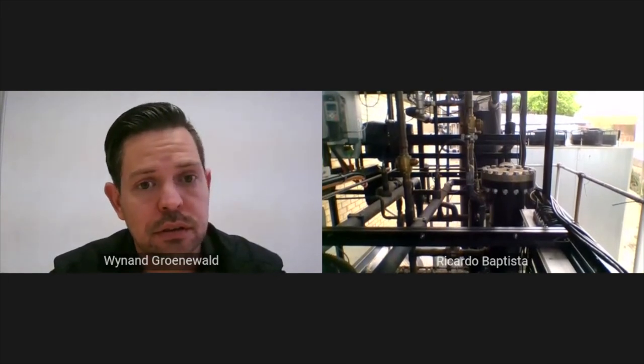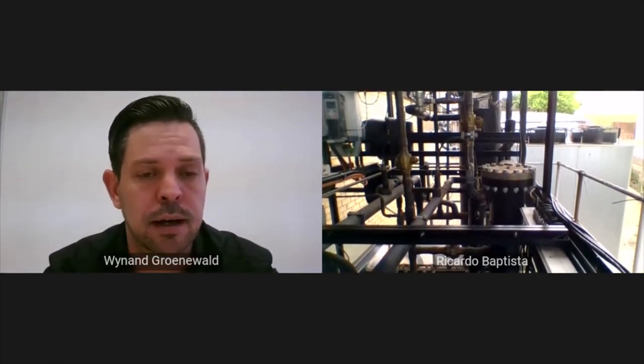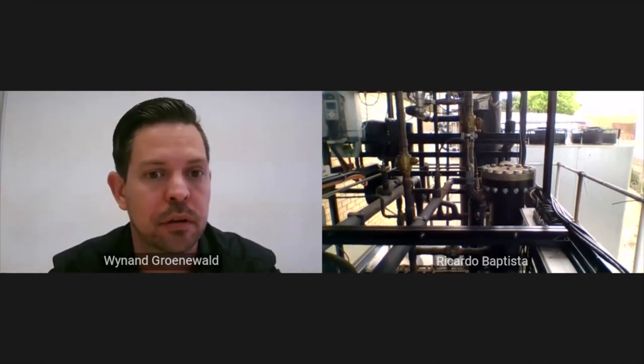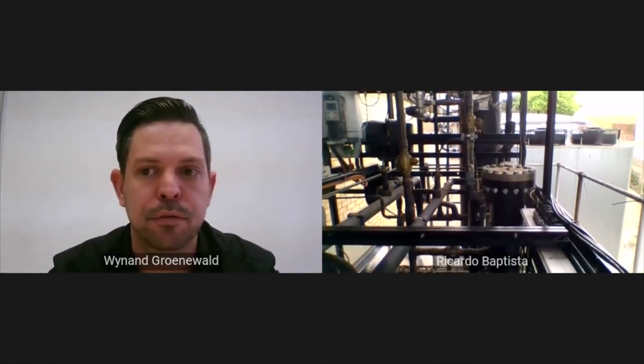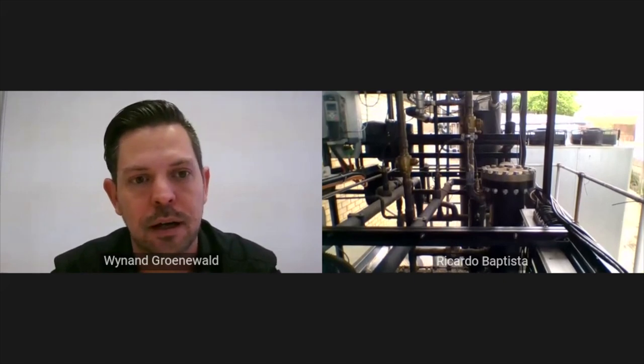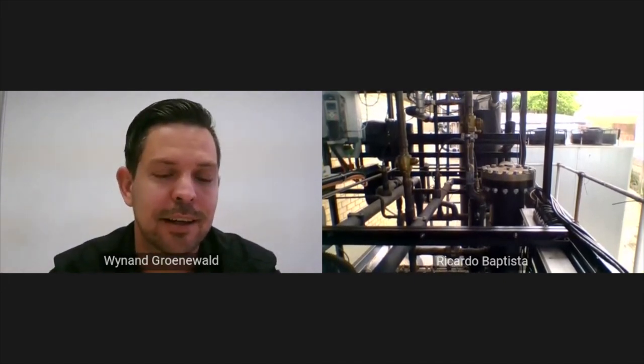When purging a CO2 system with CO2, while I'm on that topic, when starting up a system, it's always good to remember that CO2 has a very high triple point of about 5.18 bar. So good practice is to have vapor introduced into your system up until a minimum of 10 bar before liquid is introduced into the system. The common reason for that is if liquid is introduced into a system below 5 bar, dry ice will form, and that can take you quite some time to get rid of within the system.